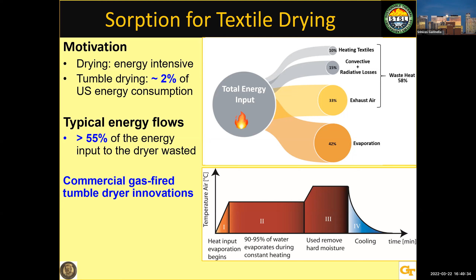Is there a way we can use this phase to preheat? Well, it's not like you can take the exhaust from the dryer and put it back into the inlet, because you spend all this energy removing moisture from the clothes and putting it into the airstream. You're not going to bring that same moisture back. It's hot, but it's also moist, so that defeats the purpose.